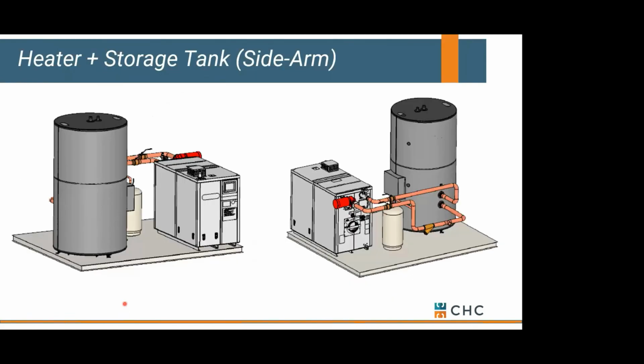Let's talk. We've been talking about tank type. Let's take that same storage tank idea and put a dedicated heater next to it, which we would tend to call sidearm, and the fact that we've got a dedicated water heater serving a storage tank. And why are we doing this? Why don't we just take a dedicated water heater and generate our 40 to 140 and meet the load out in the building? Most of the time, this dedicated water heater can't handle that 100-degree rise across the heat exchanger itself. They're usually limited to about a 60-degree rise, which means if you want a 100-degree rise out of your domestic water, you have to circulate it through a storage tank, or circulate the water that's being held in the storage tank, which is what we're doing.